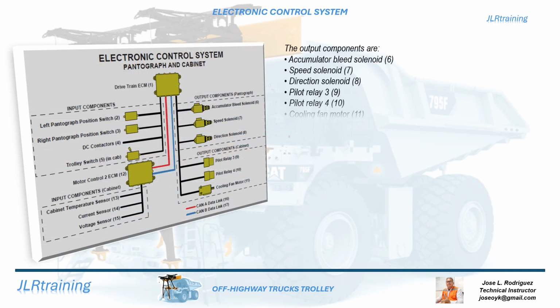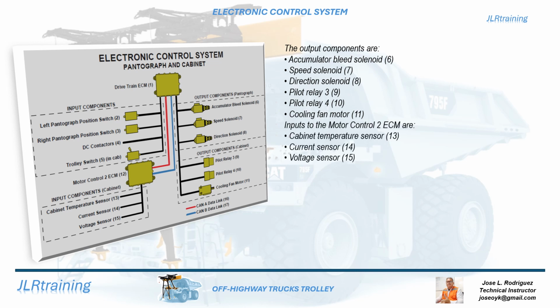The output components are accumulator bleed solenoid, 6, speed solenoid, 7, direction solenoid, 8, pilot relay 3, 9, pilot relay 4, 10, cooling fan motor, 11. Inputs to the motor control 2 ECM are cabinet temperature sensor, 13, current sensor, 14, voltage sensor, 15.